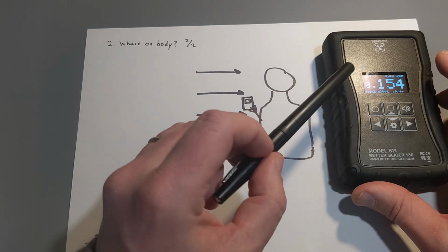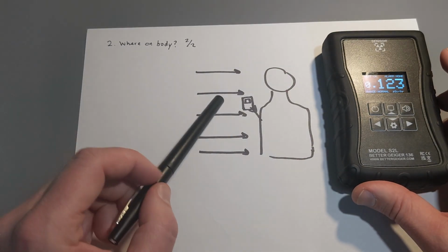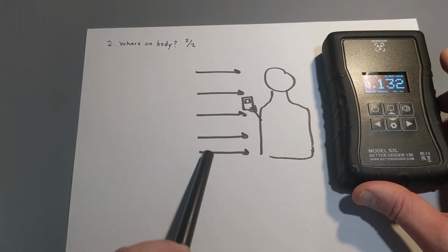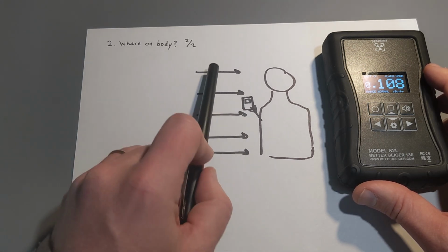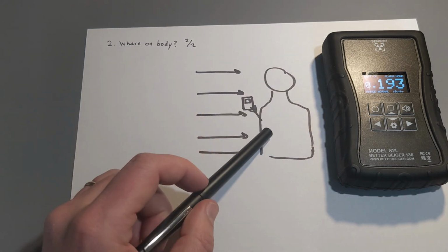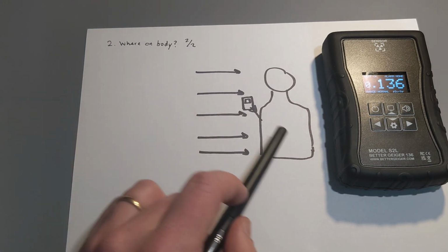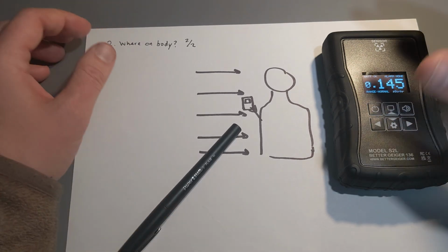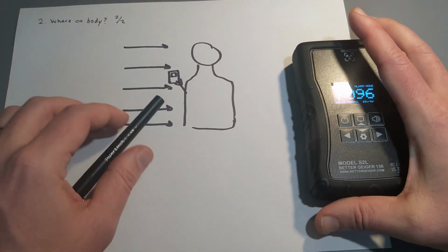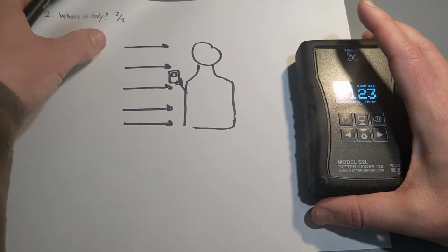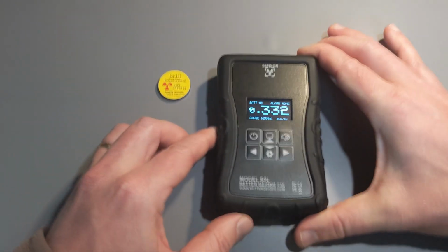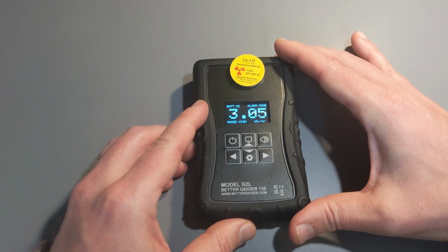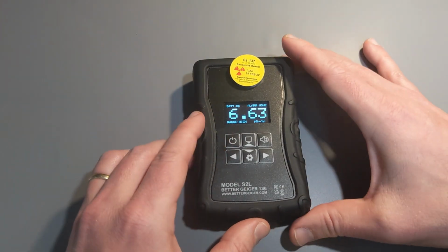When it gives a dose number, this device is saying whatever it's measuring at this location, it assumes that everywhere is the same. So that is going from a point measurement to a whole body measurement, because this device just can't know if this is a complicated field or if it's more here or there. And that's important to consider, because the situation where this can really cause problems for people is if you have some kind of source, and this is a cesium-137 gamma source. If I put that on there just like that, the dose rate is going to go up to whatever it goes to.